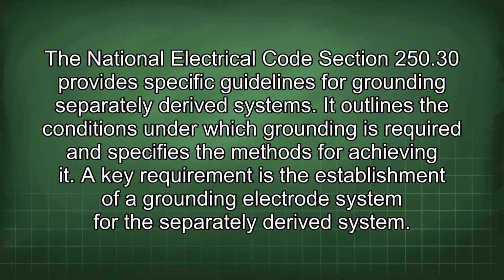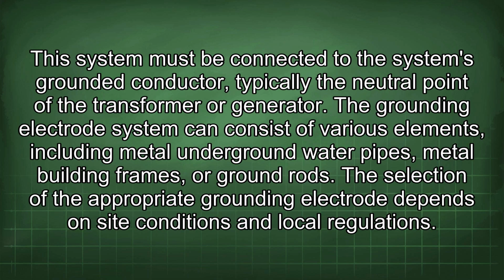The National Electrical Code Section 250.30 provides specific guidelines for grounding separately derived systems. It outlines the conditions under which grounding is required and specifies the methods for achieving it. A key requirement is the establishment of a grounding electrode system for the separately derived system. This system must be connected to the system's grounded conductor, typically the neutral point of the transformer or generator. The grounding electrode system can consist of various elements, including metal underground water pipes, metal building frames, or ground rods. The selection of the appropriate grounding electrode depends on site conditions and local regulations.